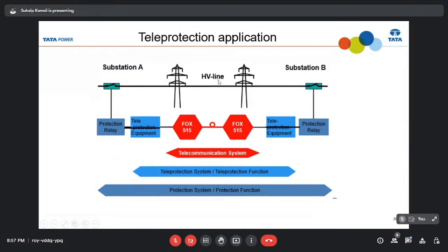The standard maintained through my electrical testing team requires a maximum of 50 milliseconds of delay to eliminate any fault. But that 50 millisecond requirement is easily satisfied by this system's 7 millisecond speed, so any lagging or delayed signal is definitely eliminated. This shows how fast, robust and reliable the system is, which is required for protection of my EHV line.